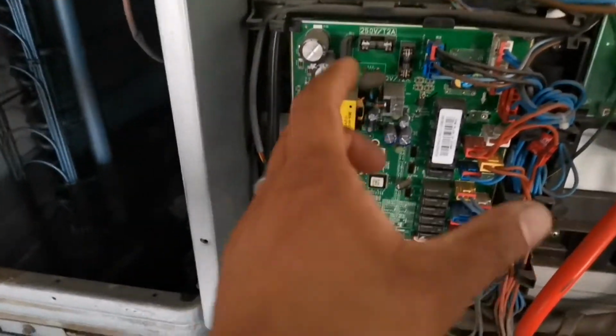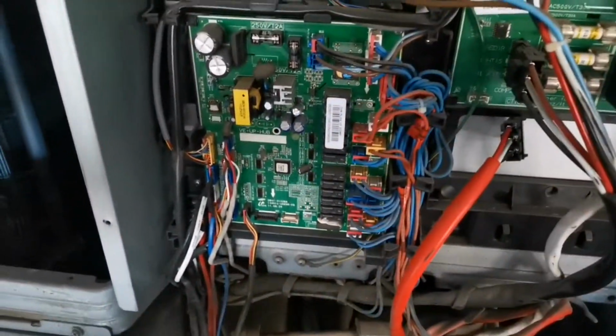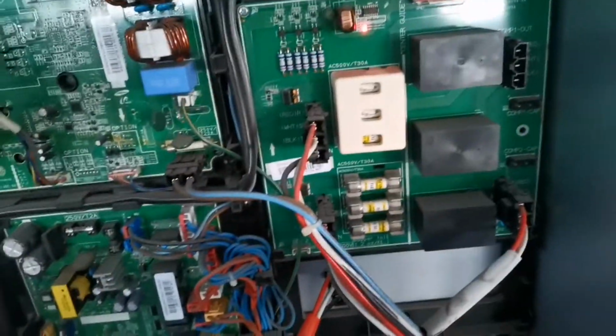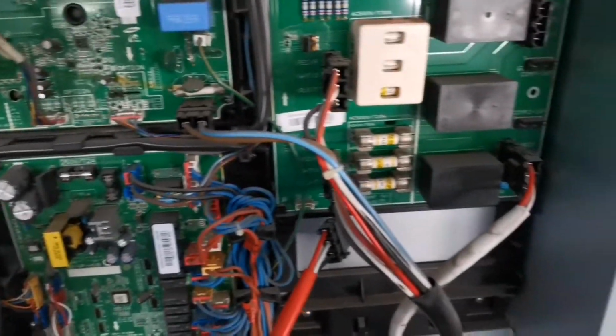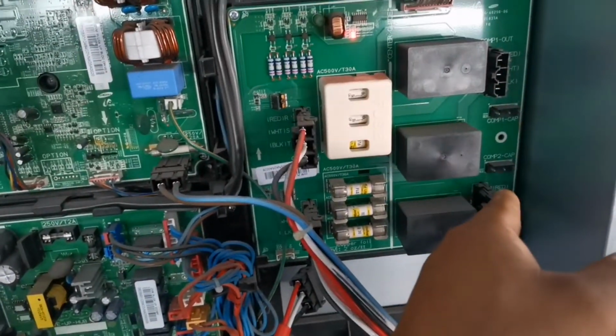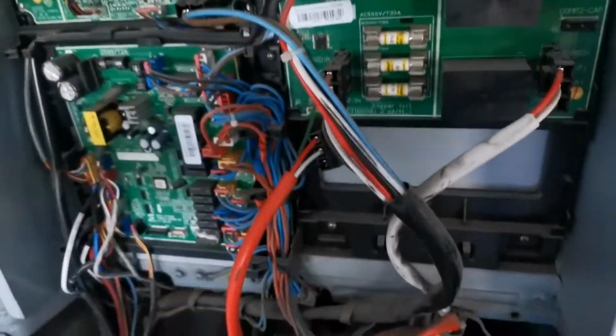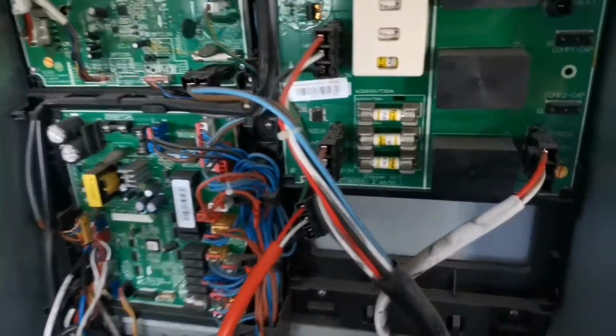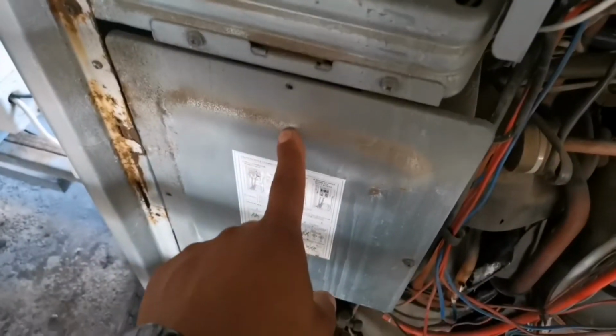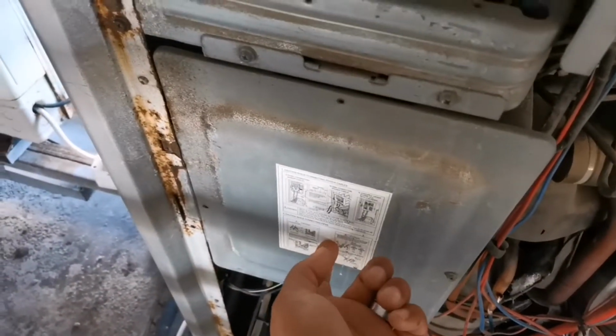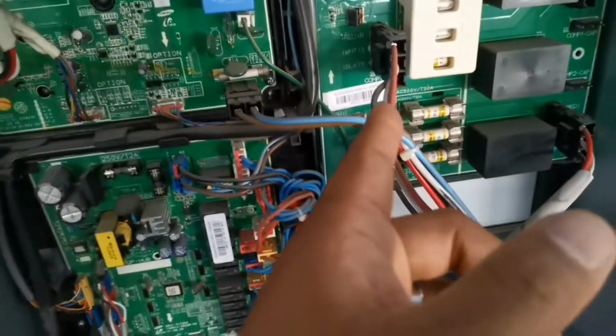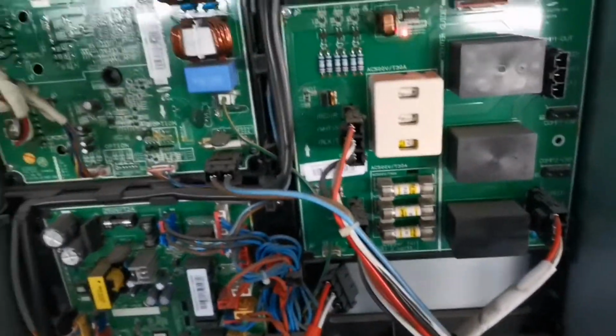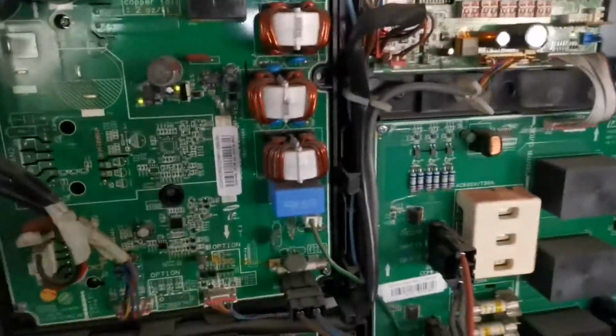This one right here is your hub board. On the DVM-S system it's a much longer PC board, and this one right here is your CT compressor board. So this is the two outputs for the compressors, and here is your inputs, and there are the fuses. There's another board in here where your electrical terminals are as well. We'll go ahead and start there. Start by checking incoming power and verifying that our supply is correct, and then we'll check it over here, go through our fuses, and then we'll start ohming out these compressors and see what the issues are. Cool.